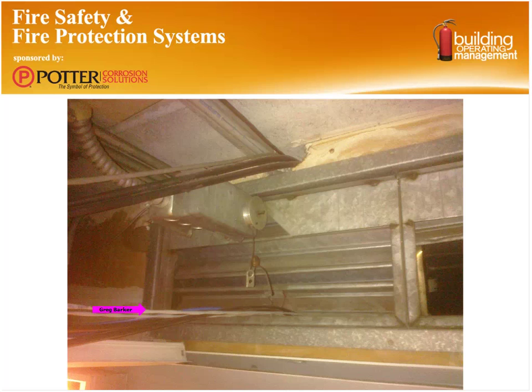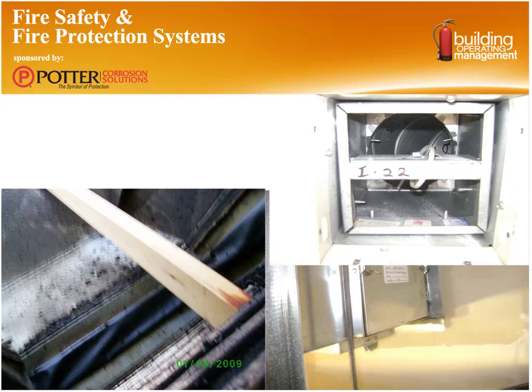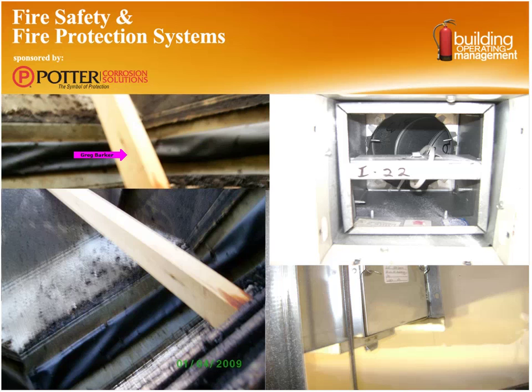If you look right here, in this damper case, this is a real common issue. The cabling guys love to use these dampers as a place to pass wires through. So something for you to keep in mind is, if you're hiring a cabling company, make sure you keep them under control and watch what they're doing, and make sure any good cabling company should not be using a fire damper or fire opening for their cable pass-throughs. Some others that we have here, we found pieces of wood. Some guys jammed a piece of wood in one of the dampers to hold it open so that it doesn't close, or the motor had failed and they just cock it open.